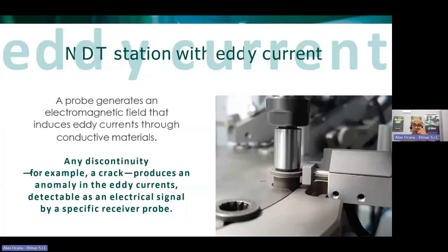All right, let's take a closer look at how eddy current crack detection works in practice. Until about 2 years ago, eddy current was the only effective method for crack detection. On our machines, we routinely use eddy current systems, such as Marposs or IBG. Most of you are likely already familiar with it, but I'll briefly recap the technology. What we have here is a dedicated inspection unit. You can see it in the photo, equipped with one probe or sometimes two, depending on the configuration.